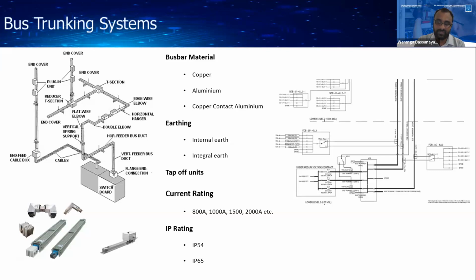Therefore, when you are inspecting this low voltage system, you have to clearly see whether proper terminations are done. We cannot allow aluminium conductors to terminate directly to the circuit breakers without a bimetallic lug or a copper-contact aluminium system. So another important point is that we have to examine those things.